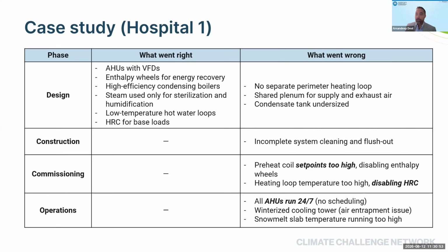And last but not the least, operations is a critical factor in all of these case studies. These hospitals were originally designed, even in the energy model, to have the air handling units and ventilation systems set back or scheduled off for spaces which are not occupied 24/7. However, in operations, that didn't happen. Everything ran 24/7. As a result, there was an increase in the ventilation energy and an increase in the heating and cooling energy for the system. So these are what went wrong with these hospitals.